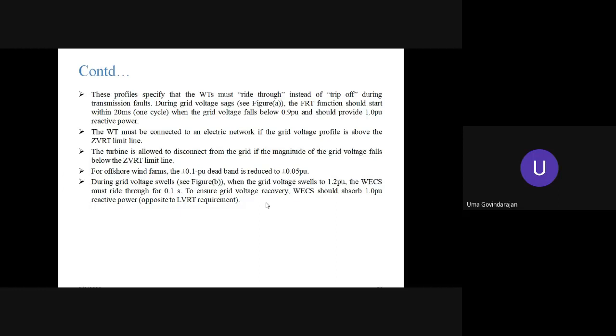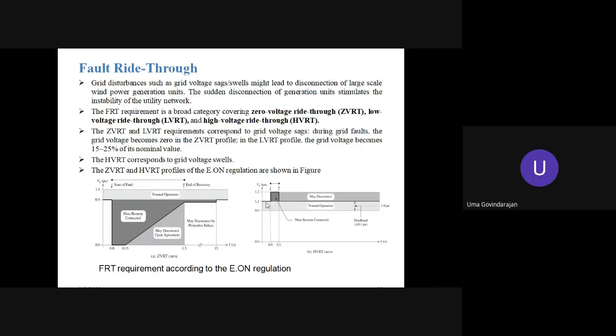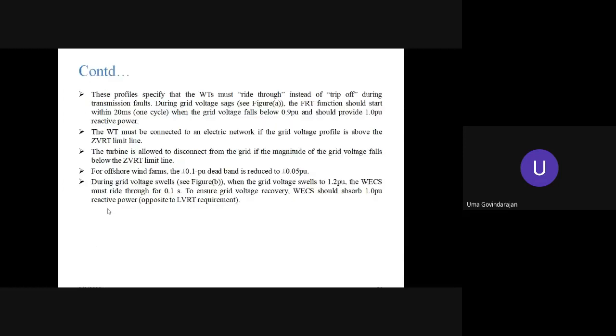We are giving a variation of 0.9 to 1.1 as the normal operation in the previous diagram. So the variation in the grid voltage is from 0.9 to 1.1. 0.1 variation is allowed for onshore. For offshore, it is very limited, to 0.05 per unit. During grid voltage swells, when the grid voltage swells to 1.2 per unit, the wind energy conversion system must ride through for 0.1 second, must stay connected for 0.1 second.